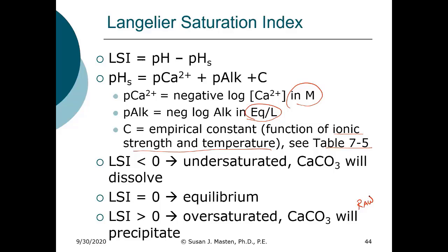The treatment that was used in Flint, which included ferric chloride coagulation and lime softening, resulted in a treated Flint River water that had an LSI that was significantly negative. And when I say significantly negative, I mean negative 1.5 and beyond.